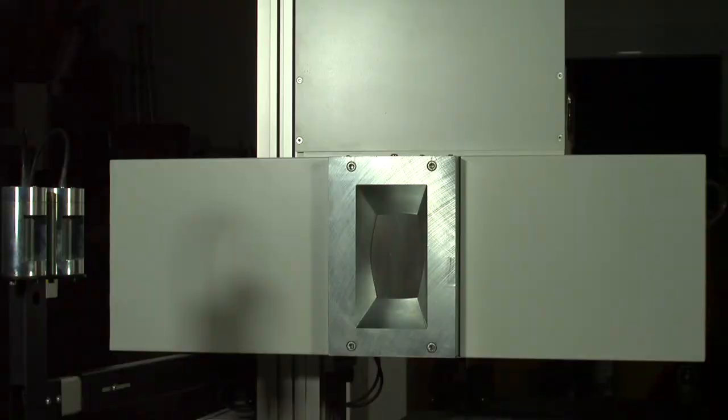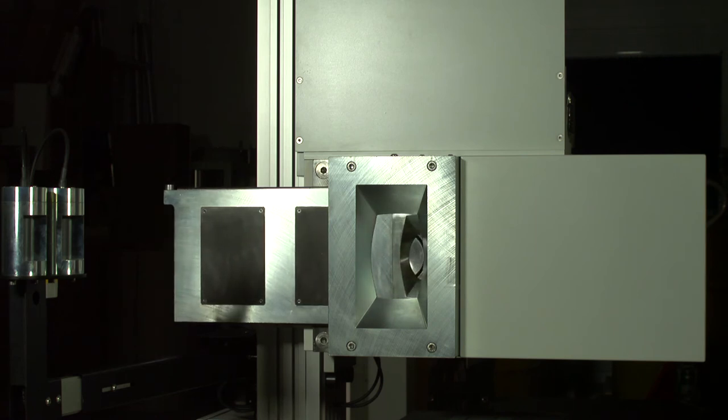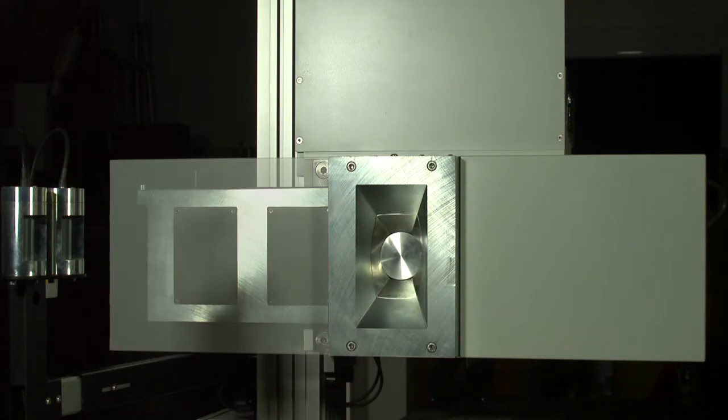In addition, two automated tungsten filters are incorporated into the body of the collimator. Either one or other filter will be deployed if the drum contains even higher activity, resulting in a higher dose rate.